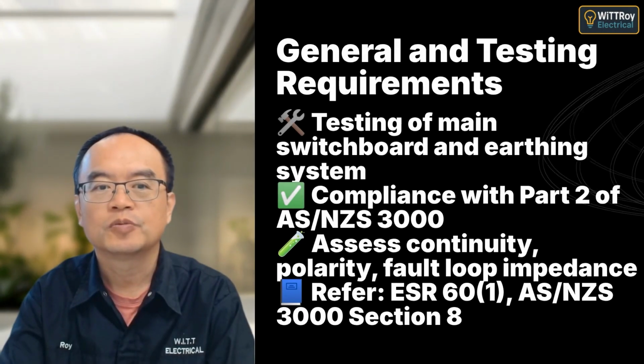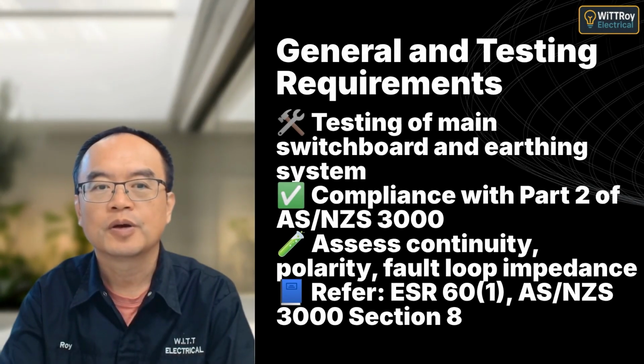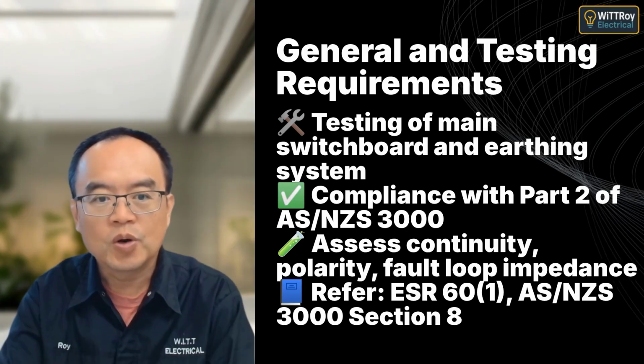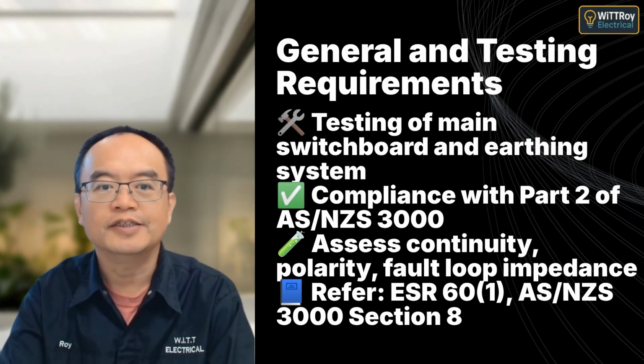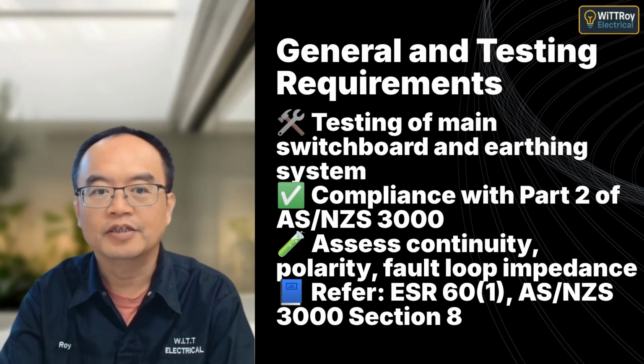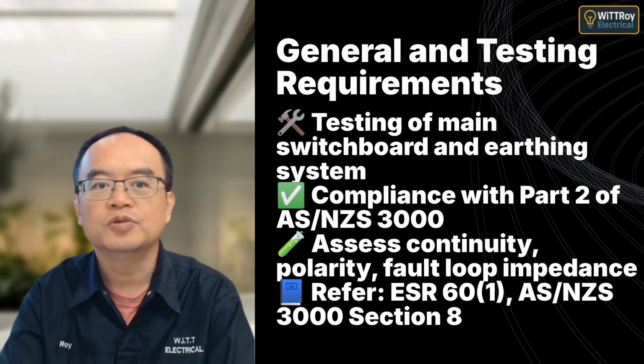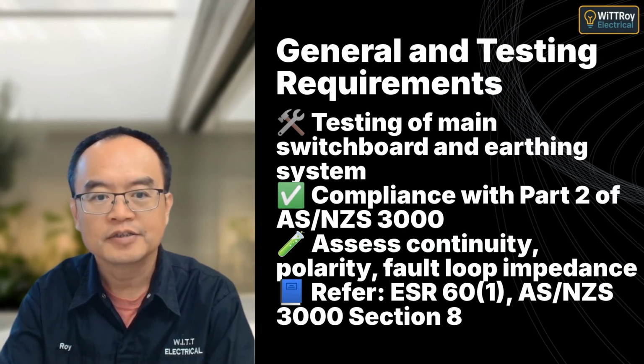Before energizing, switchboards must be tested to confirm safety and compliance. ESR 60(1) requires this testing to meet the standards in AS-NZS 3000. Key tests include earth continuity, insulation resistance, and verifying MEN connections.